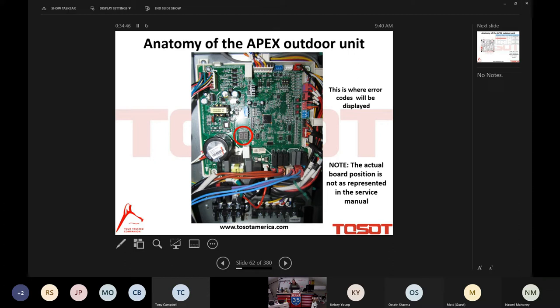And here's an example of that. There's literally a little LED screen on the outdoor unit board. It is right there, and it will give you all kinds of information that we'll talk about as we move forward. The only downside to it, I told you I'm always going to be honest and give it to you straight, is that the LED screen is on the board, and the board is internal to the outdoor unit. I really wish that Tosot could create a window where you don't have to remove the front cover of the outdoor unit in order to visually see what that LED screen is telling you. I'm hoping that's an improvement that can be made as we move forward. But for the moment, you do have to remove the front cover in order to see it.